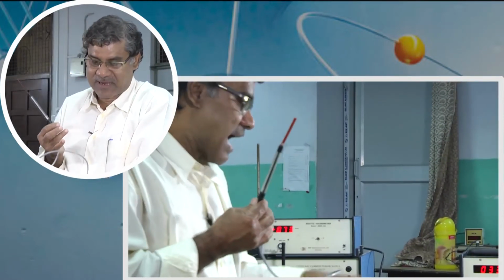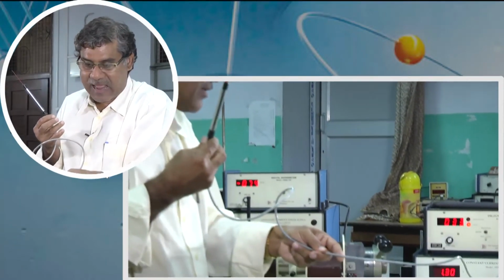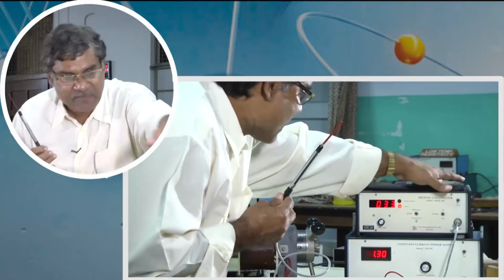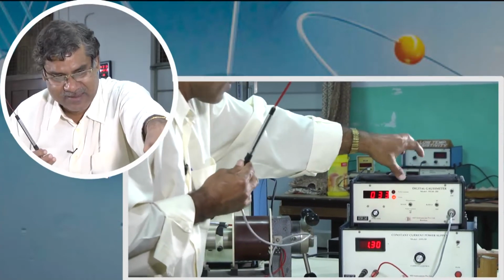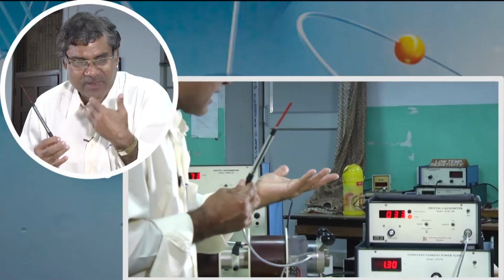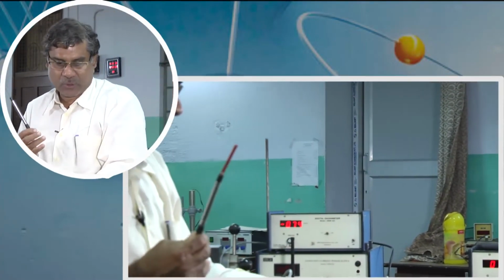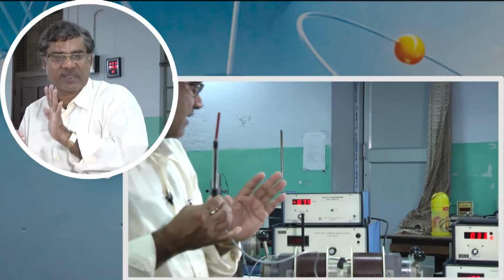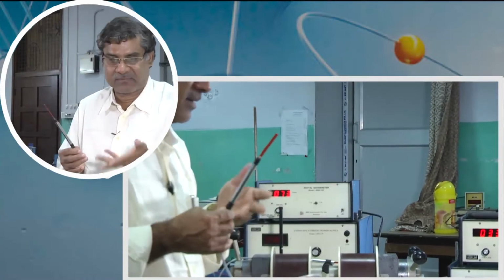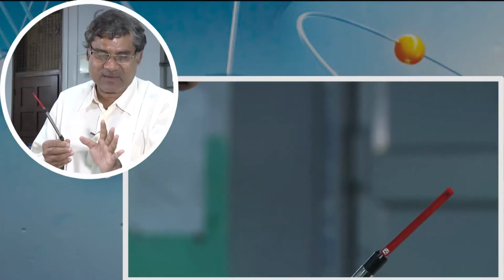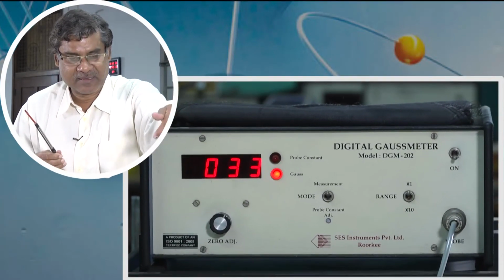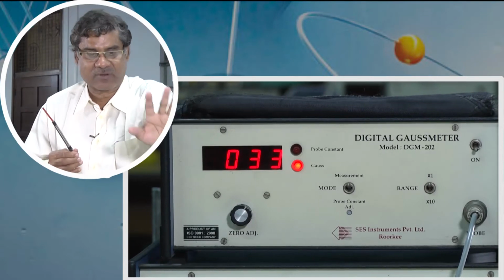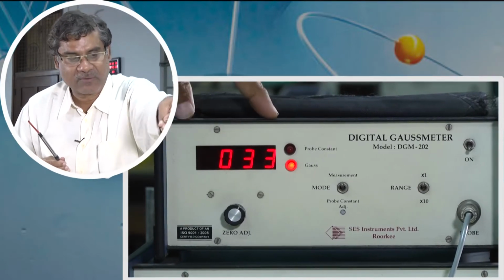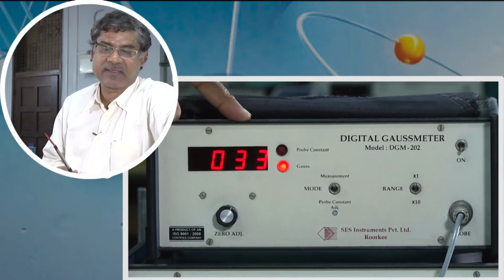The current Ix cannot be changed, because it is set inside the box, so the user cannot change it. So that Ix is also fixed, and the sample thickness and type of sample are fixed. So C remains constant, and the voltage V is divided by that constant through the electronics, and whatever value is shown here is basically the reading of the magnetic field.